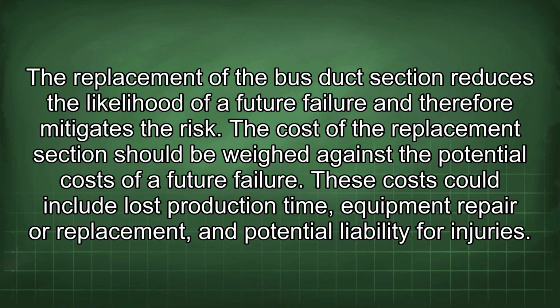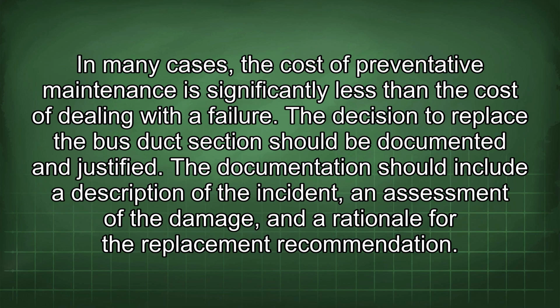The replacement of the bus duct section reduces the likelihood of a future failure and therefore mitigates the risk. The cost of the replacement section should be weighed against the potential costs of a future failure. These costs could include lost production time, equipment repair or replacement, and potential liability for injuries. In many cases, the cost of preventative maintenance is significantly less than the cost of dealing with the failure.